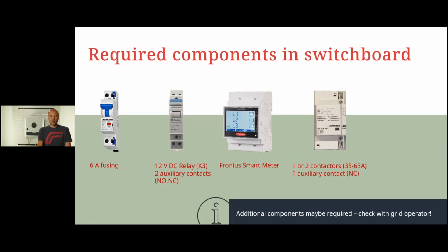Yeah, these are the required components. Basically, 6 amp fusing, a 12-volt DC relay, a small relay with 2 auxiliary contacts, one normally open, one normally closed contact, the Fronius smart meter, and 1 or 2 contactors. In some countries, you also need 2 contactors in series for higher safety. Usually in Austria, for example, we need only one contactor with 35 to 63 amps and 1 auxiliary contact, a normally closed contact, to give feedback to the inverter if the contactor is off or on.